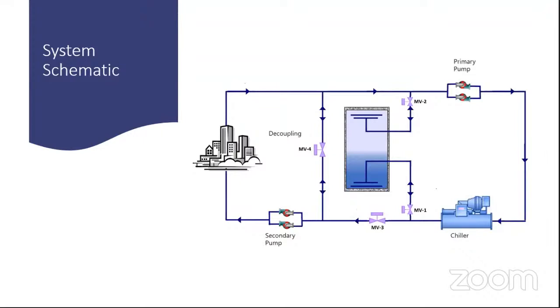Because a diffuser is not present there, turbulent mixing will happen, and it might spoil 70-80% of the water already. You want to draw 7 degrees centigrade water, 9 degrees centigrade water, but your 15-degree return came and affected all your 7-degree water and turned it into something like 10, 11 already. So what are you left with? This is something which is not taken into account in a buffer tank. However, in a stratified tank, the thermocline is separately taken into account, and the arrangement of diffusers is there. If you ask me, the right way to store chilled water would be a stratified thermal storage tank. That is technically the most correct method of storing chilled water. That's my answer.